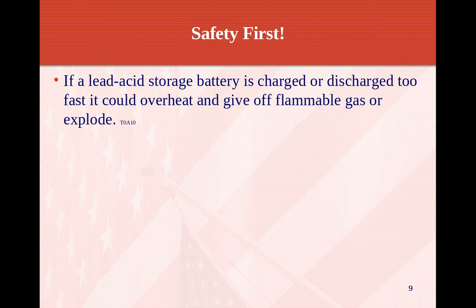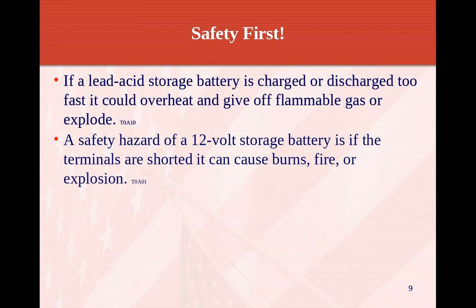If a lead-acid storage battery is charged or discharged too fast, it could overheat and give off flammable gas and explode. Okay, so when you charge or discharge it very fast, it produces hydrogen. And hydrogen is explosive. So again, you want to charge your batteries in a ventilated area. If you have a failure in your charger and start charging too quick, it'll vent off hydrogen gas.